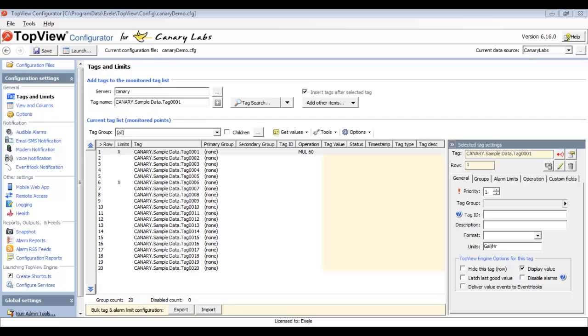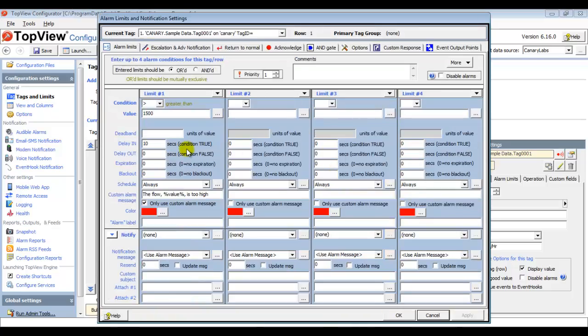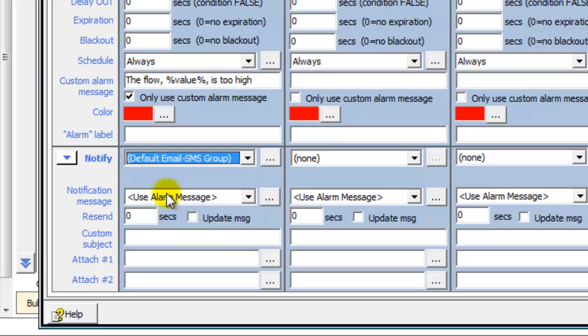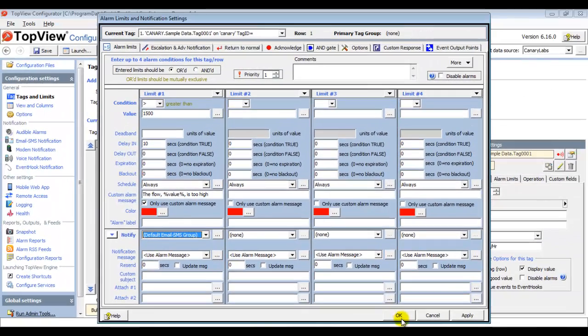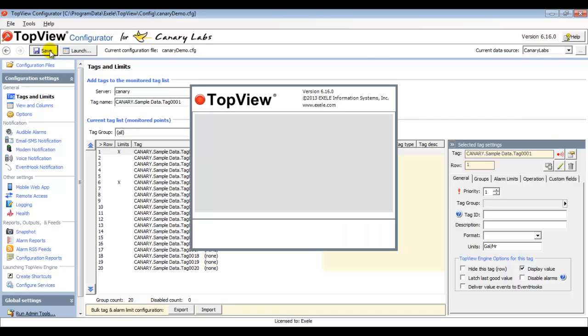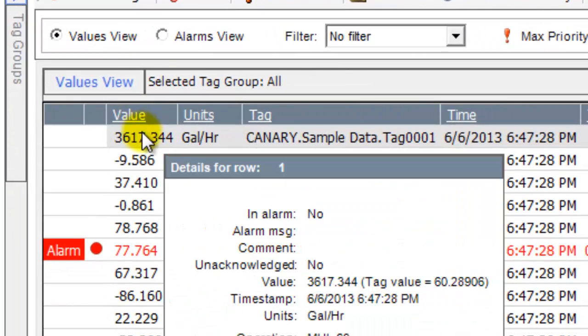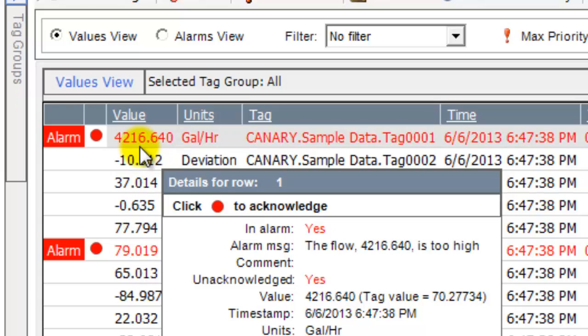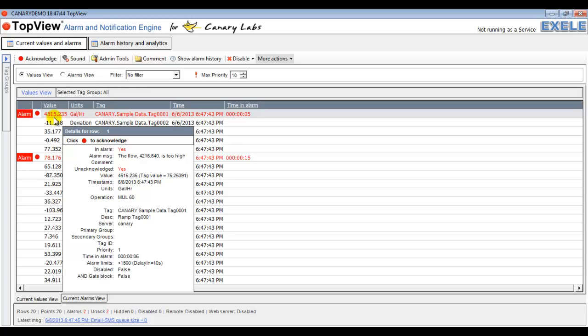The last step is to configure which alarm should send email notification. I will configure email notification for my first alarm condition — the Flow alarm, greater than 1500 for 10 seconds — to notify the default email SMS group when the alarm occurs. I click OK to apply the settings. Now I will save the configuration, and as before, the first tag should transition into alarm after 10 seconds. Now that the alarm occurred, Top View should send an email notification message to the members of the default email SMS group.